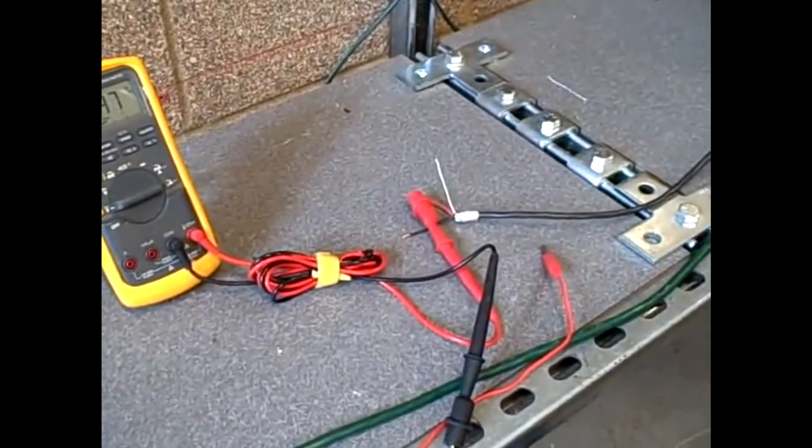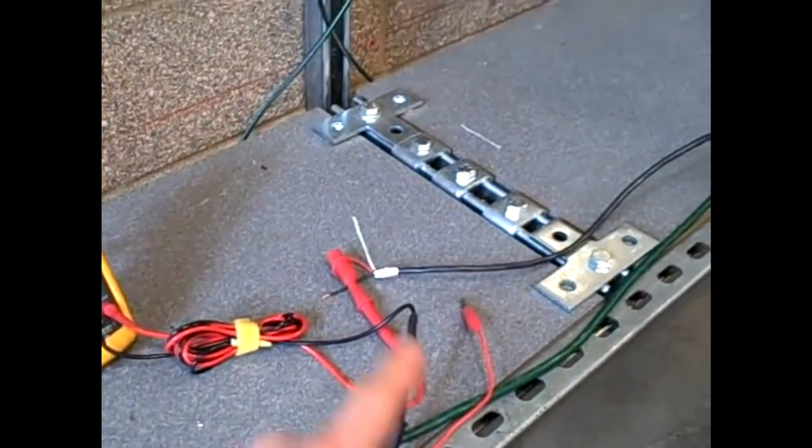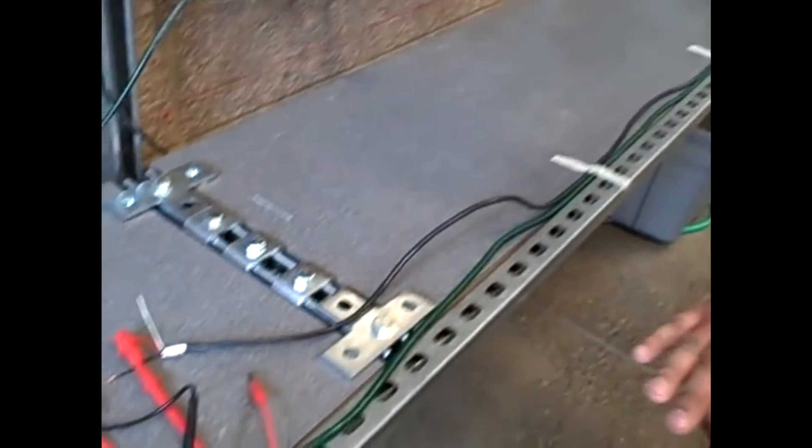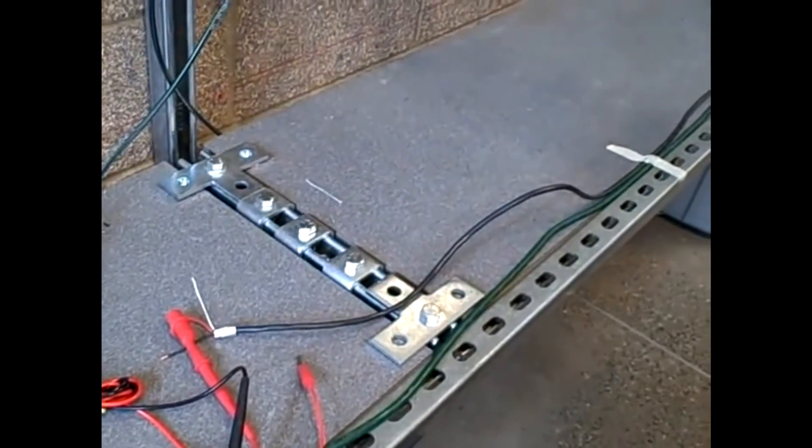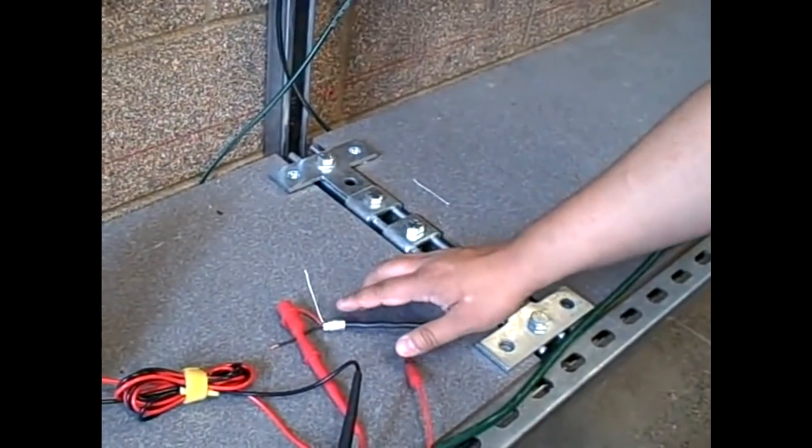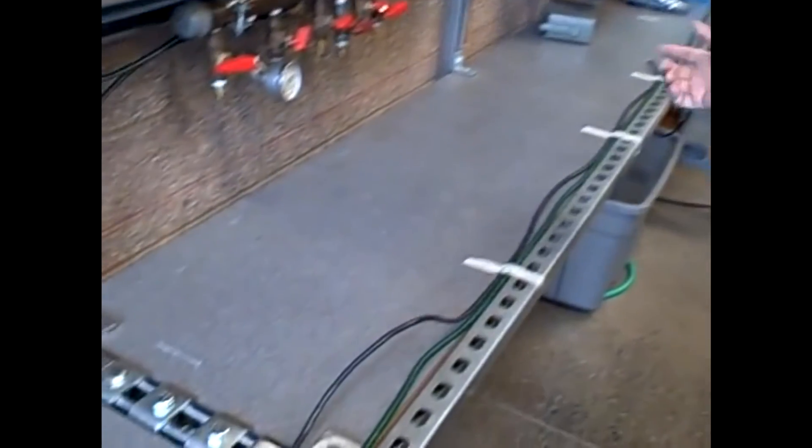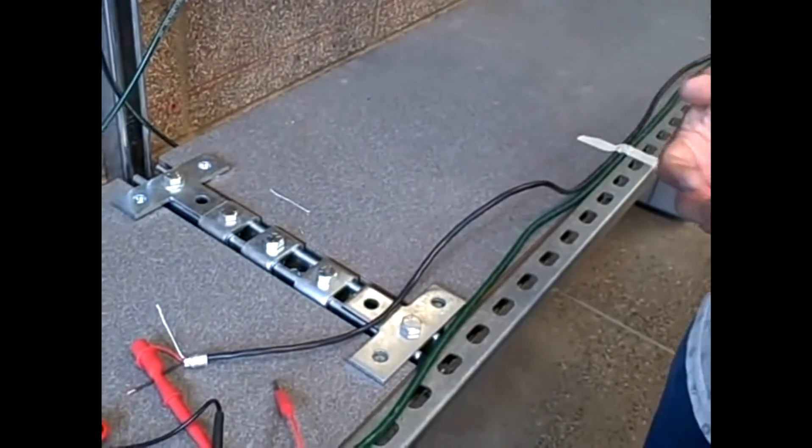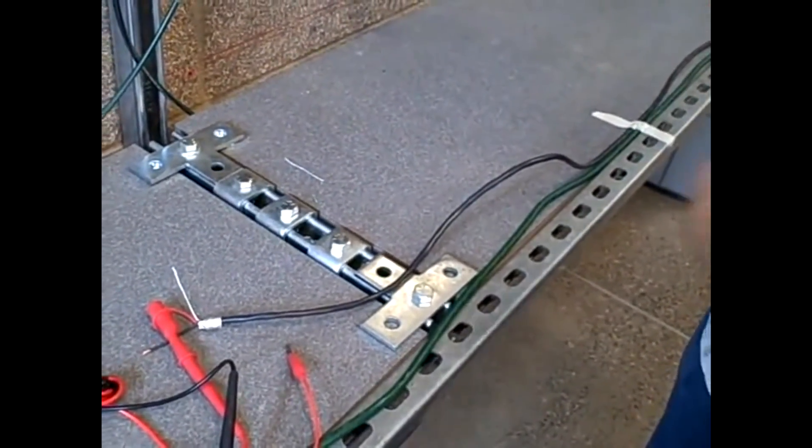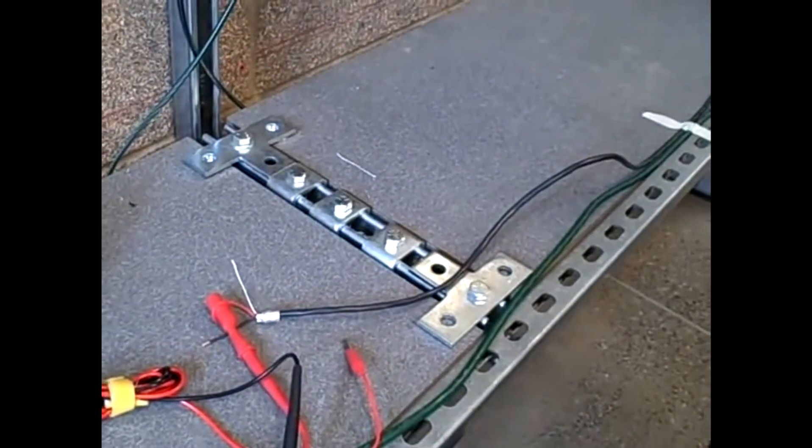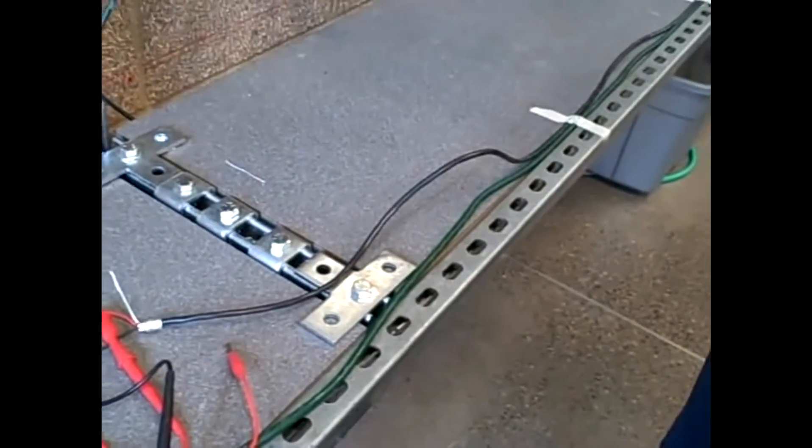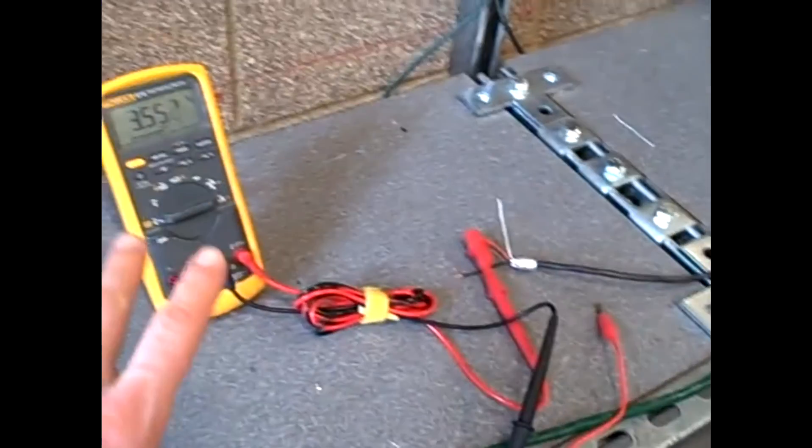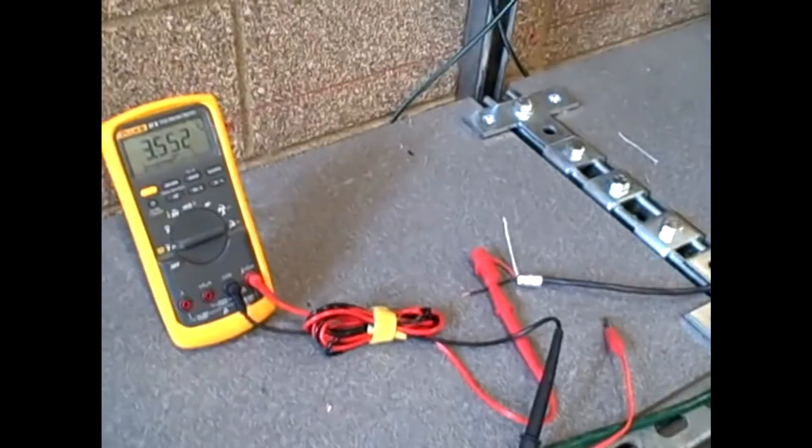There's a reason why we should only ground the signal cable at one location. We should not have the shield grounded at both ends. If you have connection at both ends of your cable, you will create what's potentially called an earth loop, which will basically return us to this problem here because of the earth conductivity. You actually have a loop where earth ground current can pass through the cable, which can cause all kinds of noise and other problems too.